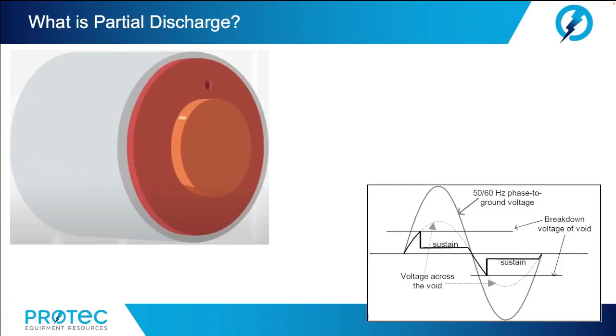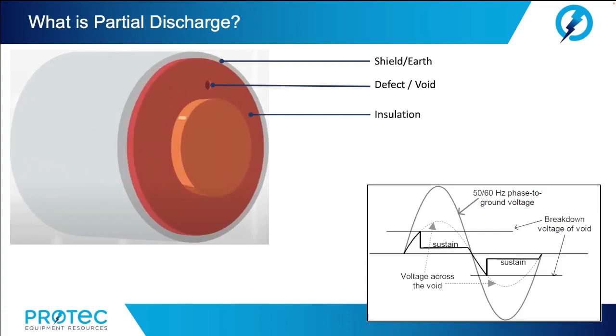Now, in our example here, we show a cable where we have the metallic or the shield earth, a defect in the form of a void, which is within the insulation of the cable, and the conductor of the cable. Now, when the voltage stress exceeds the breakdown strength of that portion of the insulating material, a partial discharge begins and continues to deteriorate that insulation. When partial discharge occurs, various physical and chemical changes may happen, which produce emissions that we can detect, localize, and characterize to provide the information needed to prevent insulation failures of medium and high voltage electrical equipment.